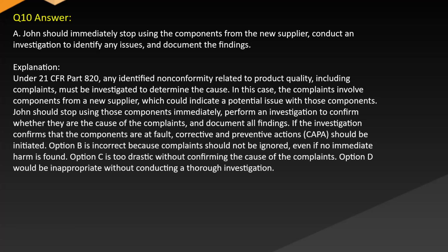Answer A. John should immediately stop using the components from the new supplier, conduct an investigation to identify any issues, and document the findings. Explanation. Under 21 CFR Part 820, any identified nonconformity related to product quality, including complaints, must be investigated to determine the cause. In this case, the complaints involve components from a new supplier, which could indicate a potential issue with those components. John should stop using those components immediately, perform an investigation to confirm whether they are the cause of the complaints, and document all findings.